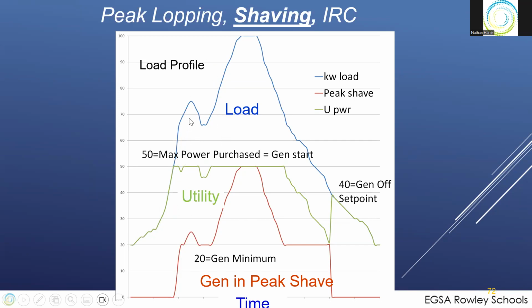So as your load comes up during the day, at some point, if you're peak shaving, you start your generator. The red is the generator power. The green is what's being purchased from the utility, and the blue is your actual load profile, how much power you actually need for your load. If you go to your utility and say, I promise I'll never buy more than 50, just a made up number here, I'll never buy more than 50 kW from you, okay, we'll put a smaller line in and your monthly charge will be less. So you say, okay, I'll agree to that. And the way I get around that is I'll start my generators up when we get close to 50.